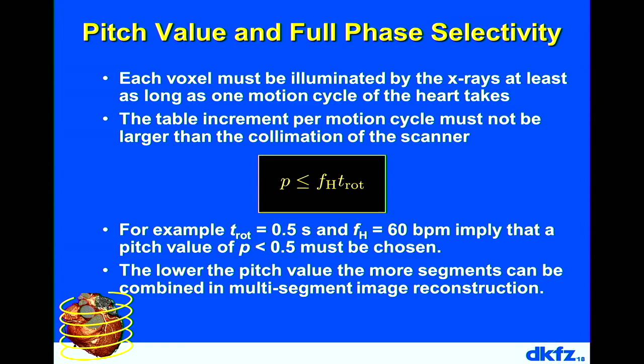For a retrospectively gated cardiac CT scan — where you decide which cardiac phase to reconstruct after acquisition — the spiral must have a very low pitch value. Specifically, each voxel of the patient must be seen by the X-rays for as long as one heart cycle takes; otherwise you cannot retrospectively choose the reconstruction heart phase. There is a constraint equation that determines this pitch value.